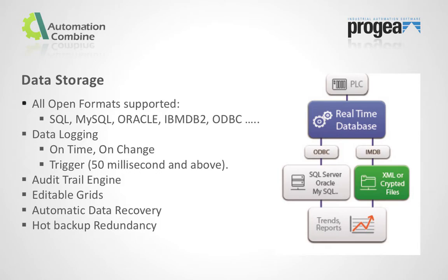Moving on to data storage. All the real-time data can be stored in SQL, MySQL, Oracle, IBM DB2, through ODBC connection, because Movicon supports open database connectivity. We also have an IMDb manager, the internal Movicon database manager, which enables us to share real-time data to a SQL database server through a data logger or recipe in the form of XML or CSV file. The IMDb manager is used for HMI solutions where a database cannot be incorporated, and it helps develop recipe data logging for limited days and generate historical trends and textual reports.